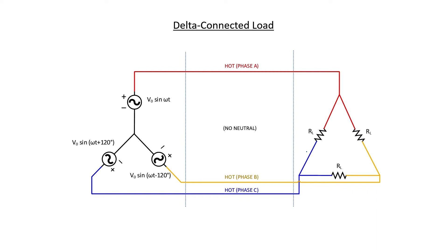Another configuration is the delta connection. So I showed three resistors in the previous view graph connected as a star. We can also connect them directly between the three phases. You'll notice in the delta configuration that we don't have a neutral wire at all. The turbine would still typically be earthed, and this might not, in all practical matters, be a turbine. It's probably the secondary of a transformer, which would be earthed at the neutral point of the star. The delta load, however, has no neutral wire at all.